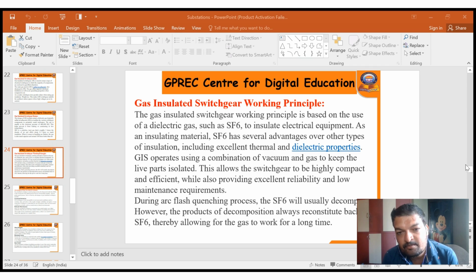During the arc flashing and quenching process, the SF6 will usually decompose. However, the products of decomposition always reconstitute back to SF6, thereby allowing the gas to work for a long time. So the property of SF6 is that it generally decomposes when arc quenching occurs or any fault or flashing occurs, but the products of decomposition reconstitute back to SF6, which is a very good property that allows it to work for a long time. This is the main property of SF6 gas. That's why SF6 gas is used as the fluid for gas insulated switchgear.